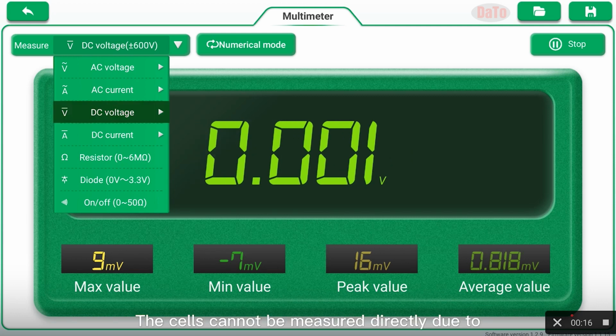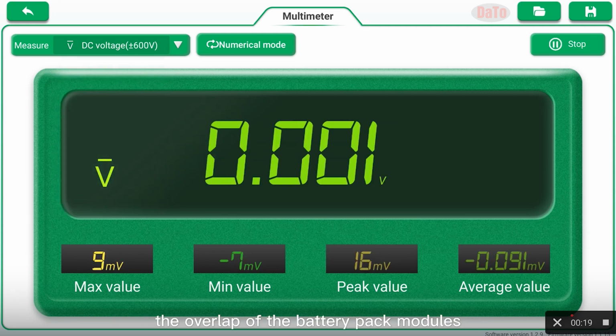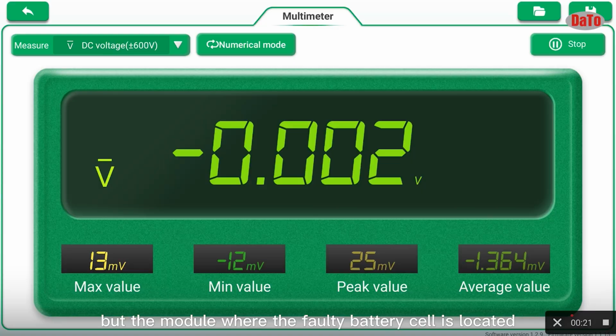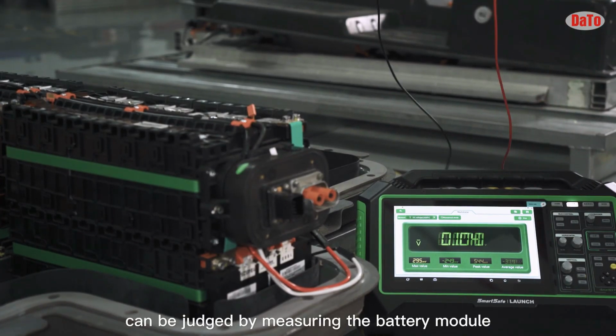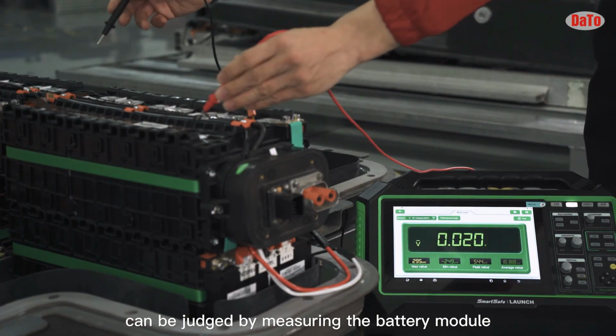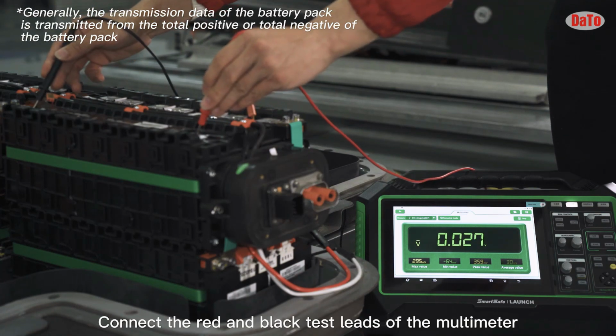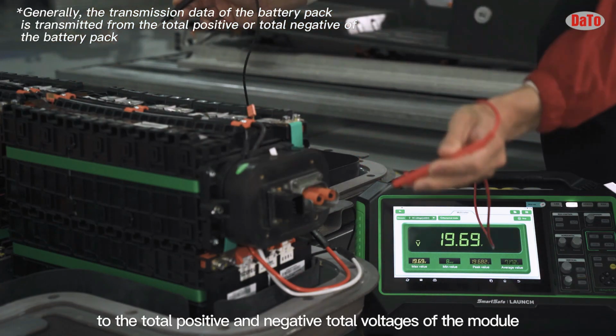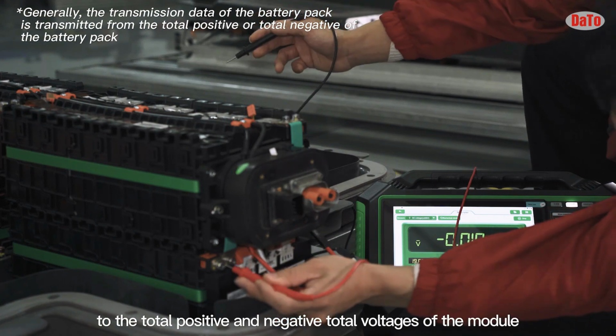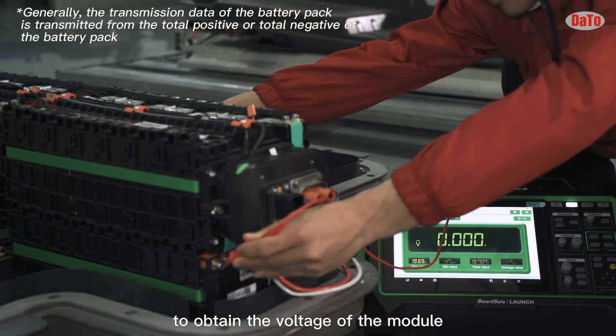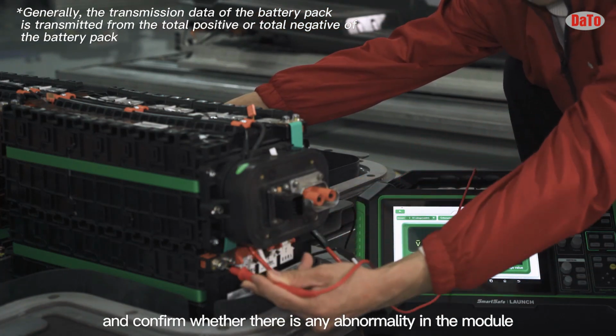The cells cannot be measured directly due to the overlap of the battery pack modules, but the module where the faulty battery cell is located can be judged by measuring the battery module. Connect the red and black test leads of the multimeter to the total positive and negative terminals of the module to obtain its voltage, and confirm whether there is any abnormality.